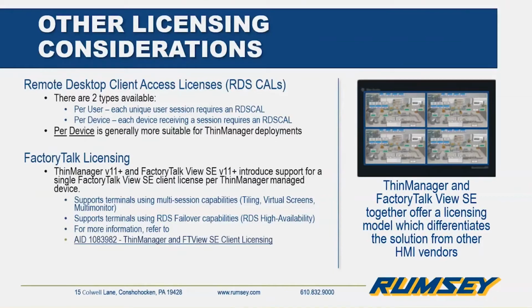What happened in version 11 of ThinManager and FactoryTalk View SE is that Rockwell has allowed us, or has created, an environment where we developed this very similar relationship as a per device licensing model. So what winds up happening here, and we'll show this in a couple of instances, is that when you're using version 11 or higher of ThinManager and version 11 or higher of FactoryTalk View SE, a client device, a terminal, will consume a single client license regardless of how many sessions you're sharing, either tiling, virtual screen, multi-monitor, whatever you're doing. And that can save some significant licensing.